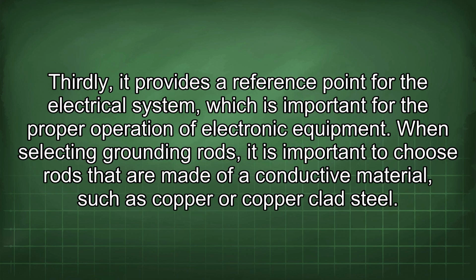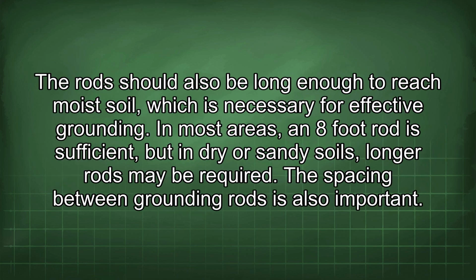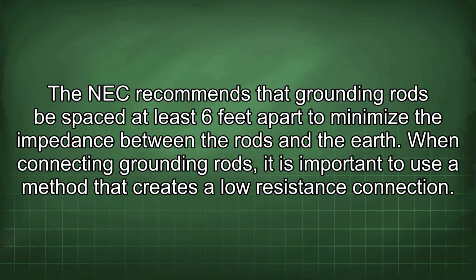When selecting grounding rods, it is important to choose rods that are made of a conductive material, such as copper or copper-clad steel. The rods should also be long enough to reach moist soil, which is necessary for effective grounding. In most areas, an 8-foot rod is sufficient, but in dry or sandy soils, longer rods may be required. The spacing between grounding rods is also important. The NEC recommends that grounding rods be spaced at least 6 feet apart to minimize the impedance between the rods and the earth.